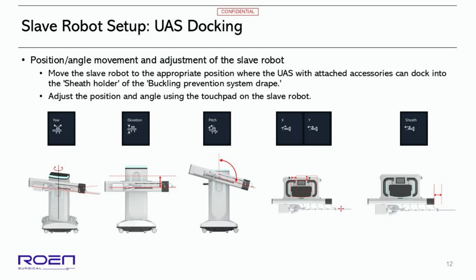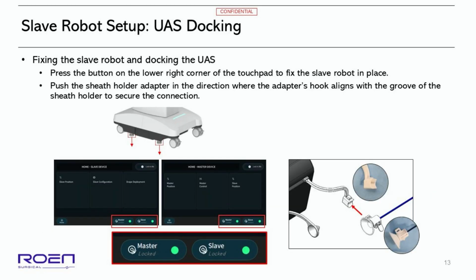Docking the ureteral access sheath. The UAS and accessories assembly must be docked into the sheath holder at the front of the buckling prevention system drape by adjusting the position and angle of the slave robot. Once the correct position is achieved, press the locked button at the lower right of the touchpad to fix the robot in place. Then insert the hook of the sheath holder adapter, aligning it with the groove direction of the sheath holder to combine.